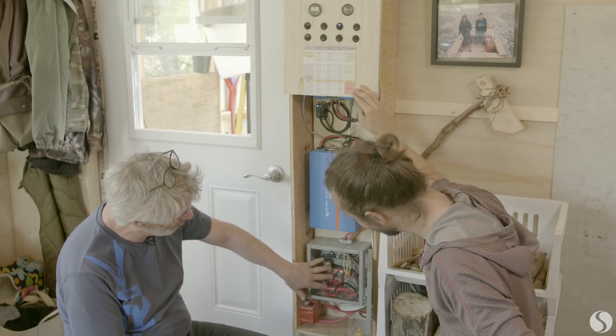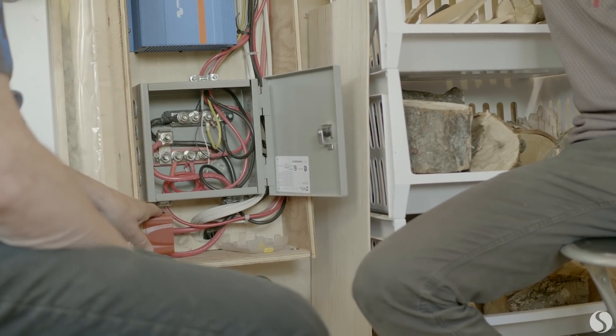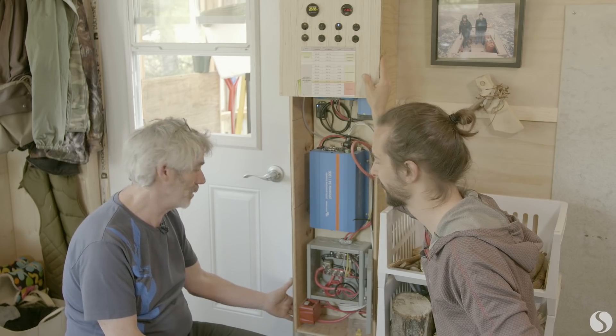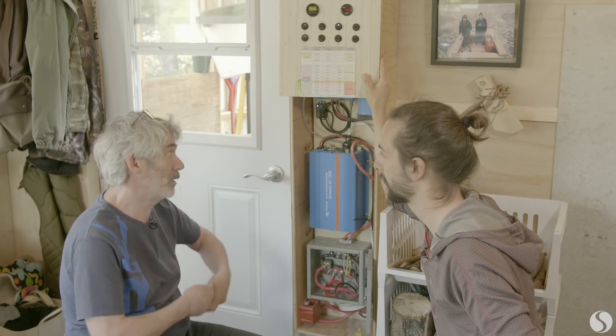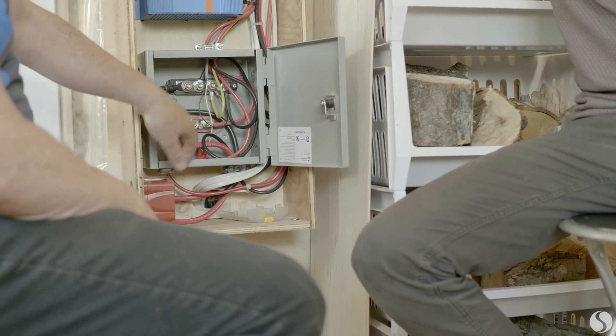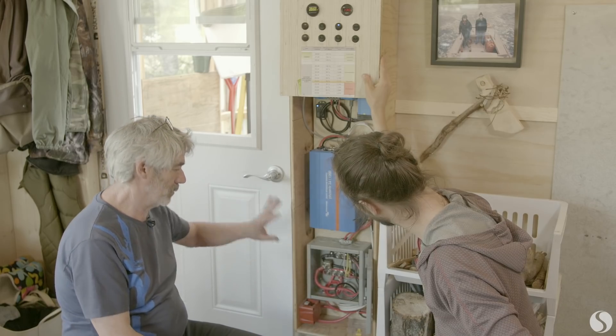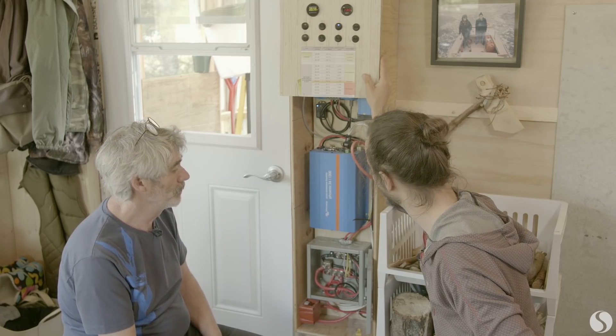Ici, c'est le point de jonction de tous les fils. Mes batteries arrivent par en dessous. On passe par cet interrupteur-là, qui est l'interrupteur principal. Si jamais il y a un début d'incendie, n'importe quoi, je le coupe. Feu électrique : on coupe l'alimentation, puis ça va s'éteindre tout seul après — extincteur, puis on éteint le bois qui aurait commencé à flamber. J'ai mes borniers — je peux mettre mes mains dedans, je ne risque rien. Tous mes départs et arrivées se font ici. Je n'ai pas 50 fils qui reviennent aux batteries — j'ai juste deux fils qui partent, puis tout se fait là.